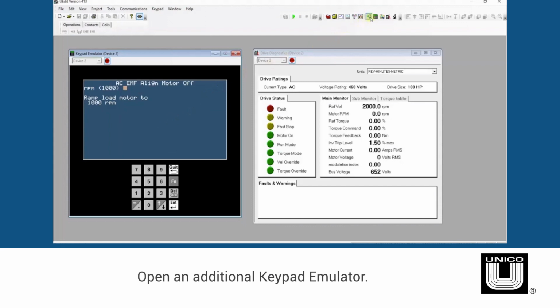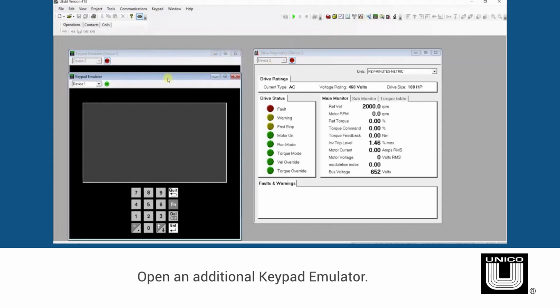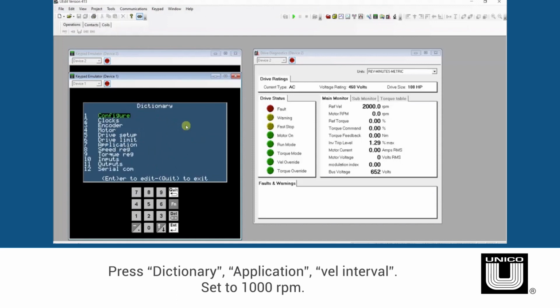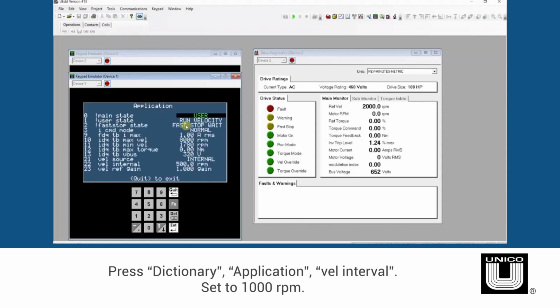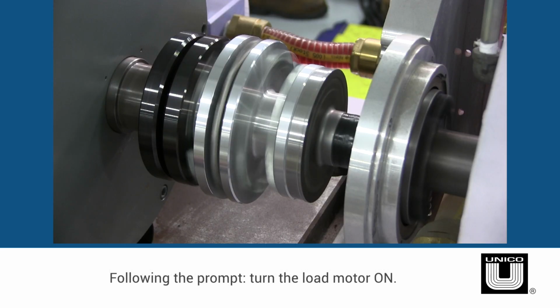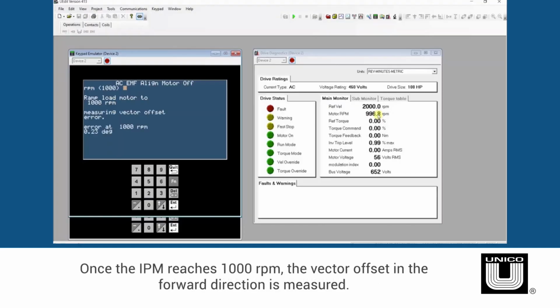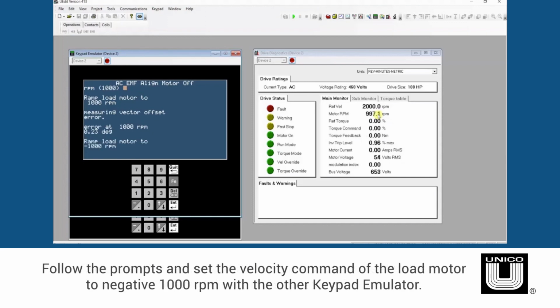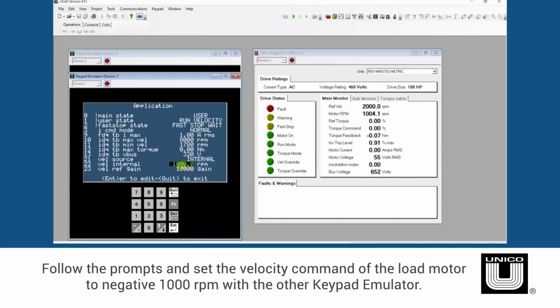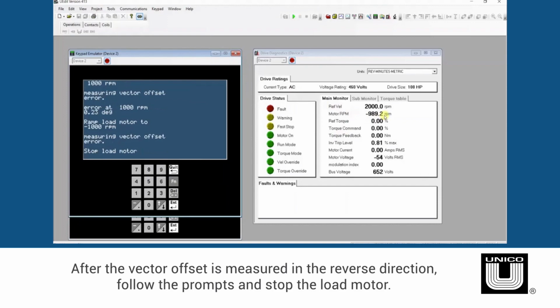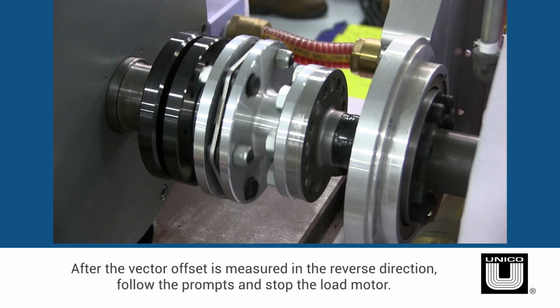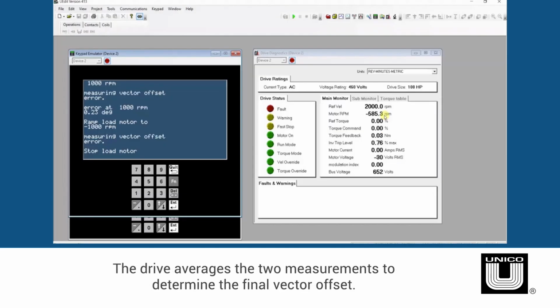For this demonstration, the IPM motor is coupled to an induction motor that's controlled through device 1. So set the velocity command of the load motor to 1000 RPM using another keypad emulator. Then turn on the load motor. Once the IPM reaches 1000 RPM, the vector offset in the forward direction is measured. Follow the prompts and set the velocity command of the load motor to negative 1000 RPM. After the vector offset is measured in the reverse direction, follow the prompts and stop the load motor. The drive averages the two measurements to determine the final vector offset.